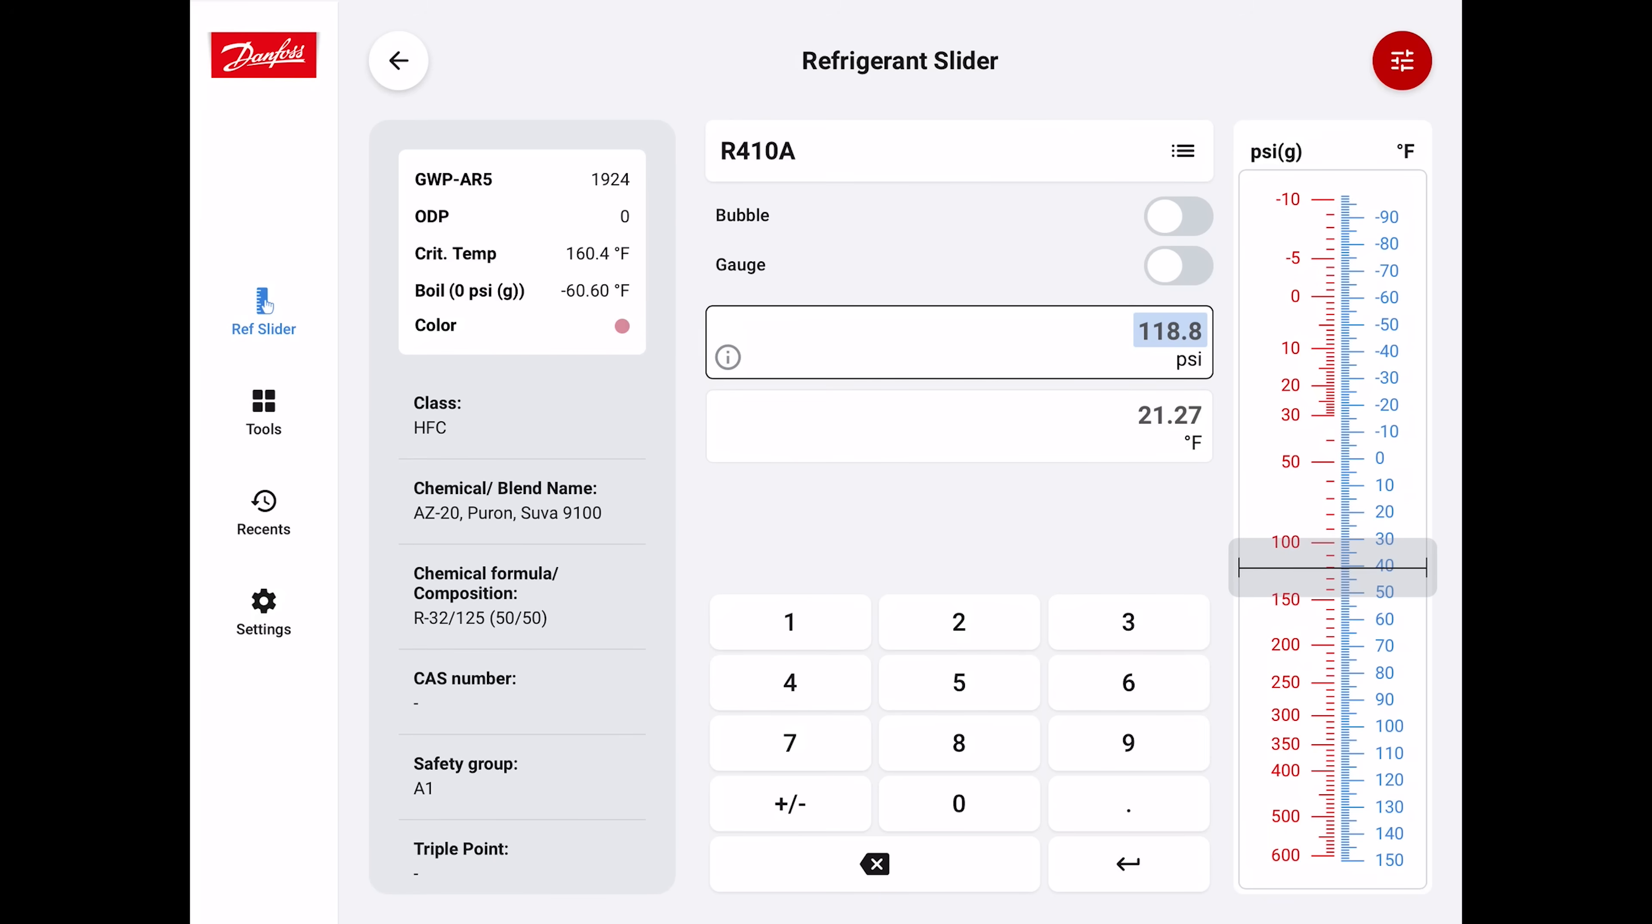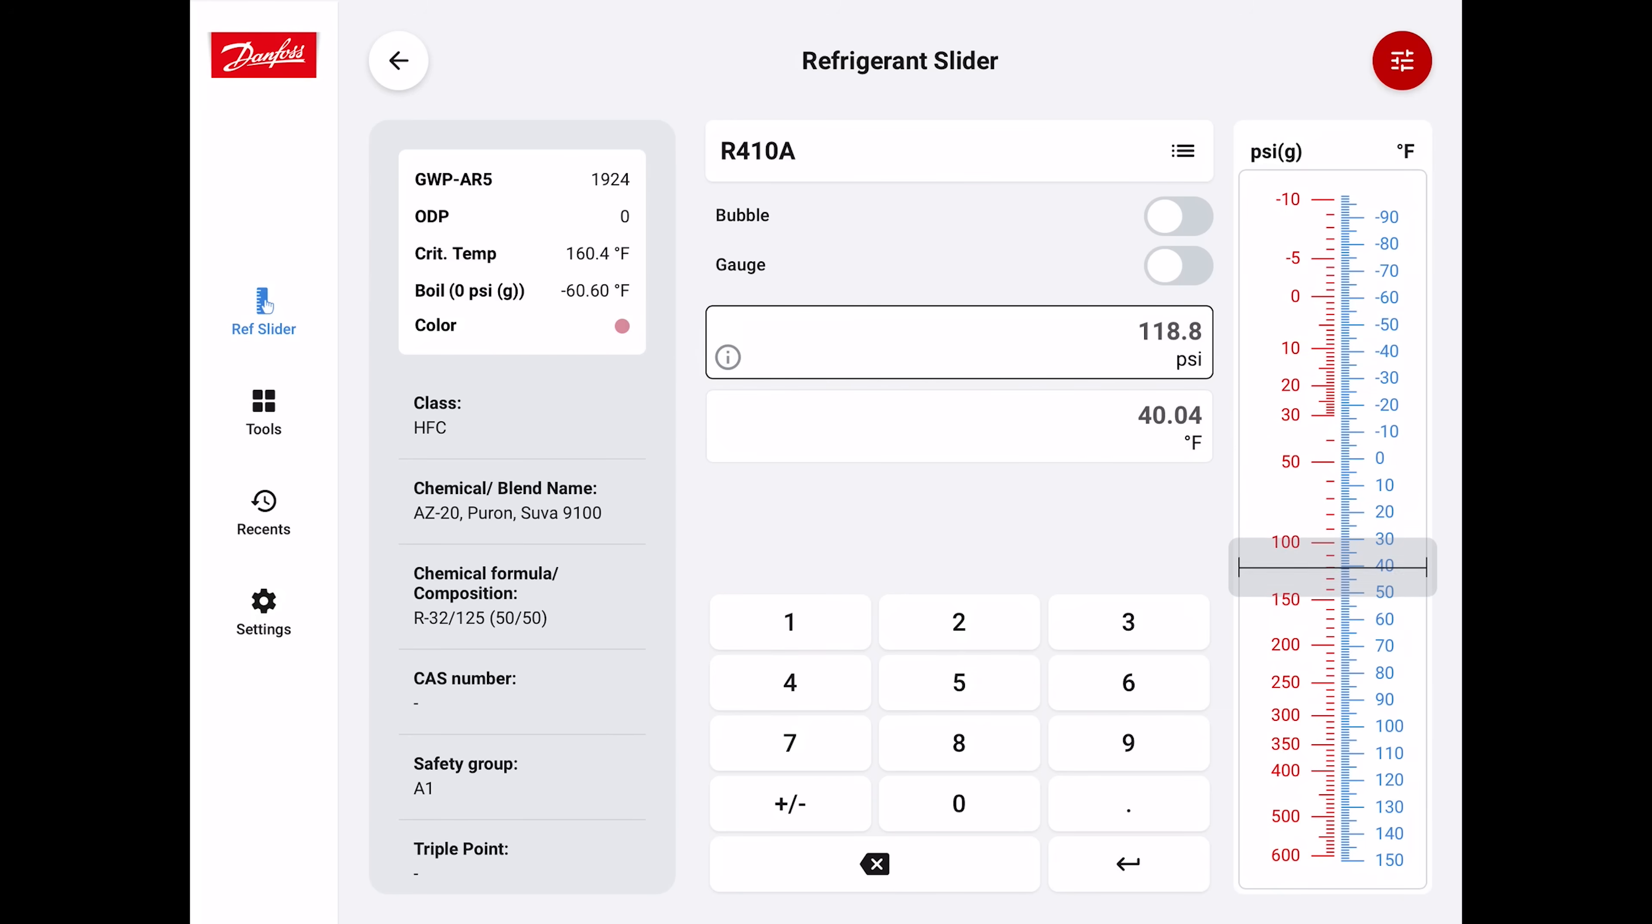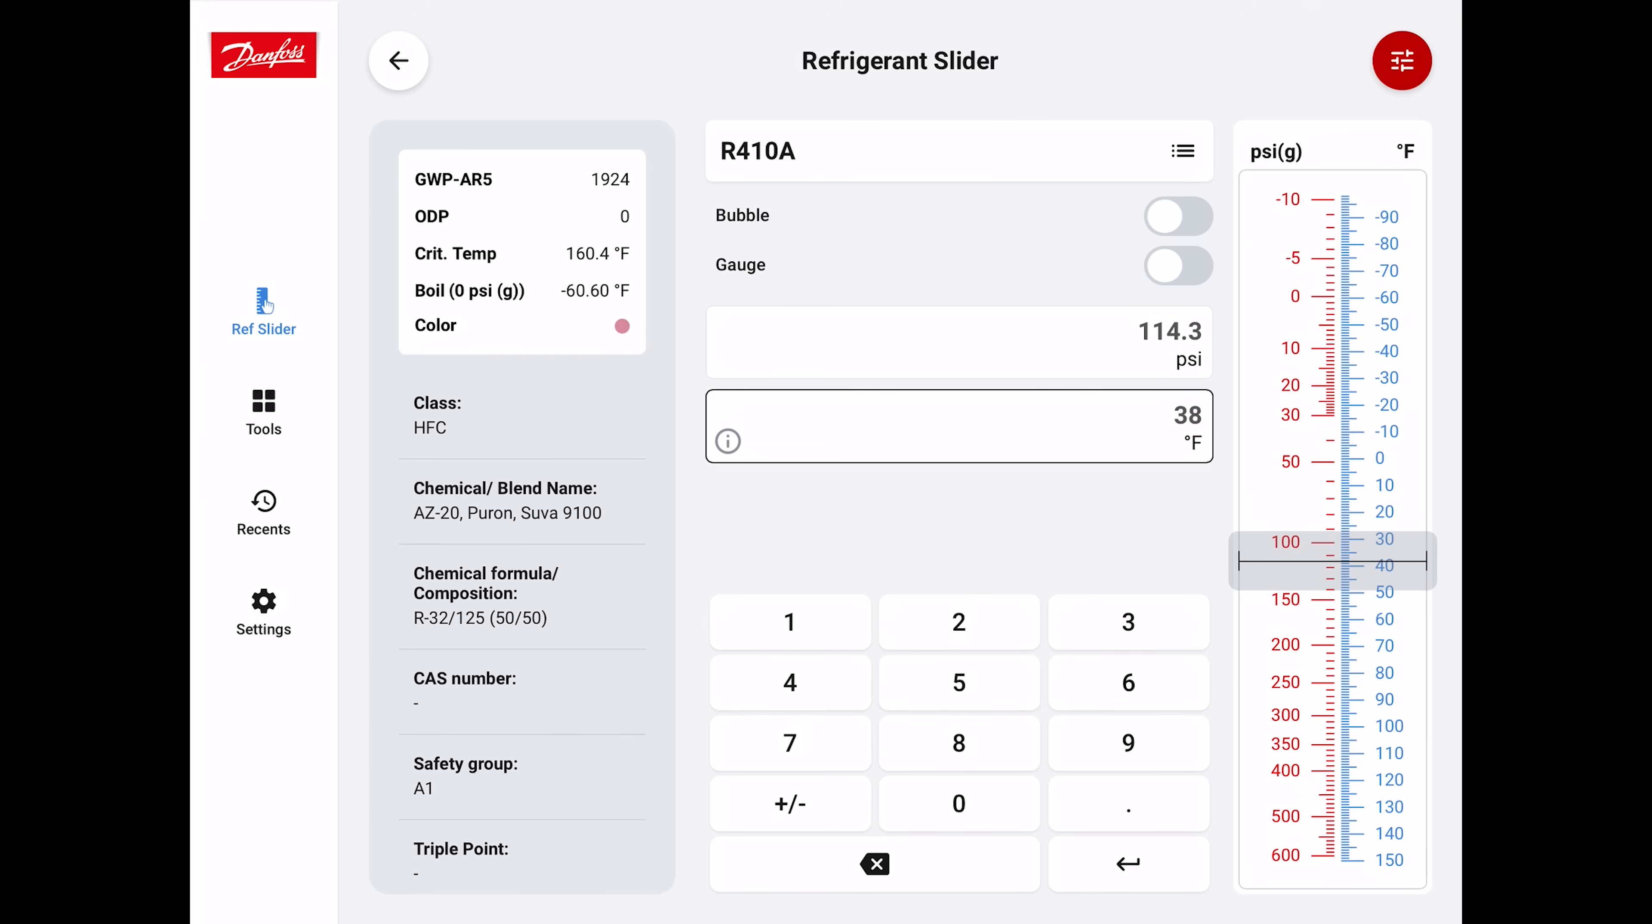We can check on the bubble or the dew. You can see that it doesn't change much depending on when you go to bubble or dew. You can go to the absolute pressure or the gauge pressure. If we enter 118 PSIG, you see it reads 40 degrees. We can change the temperature to 38 degrees, and that equals a pressure of 114.